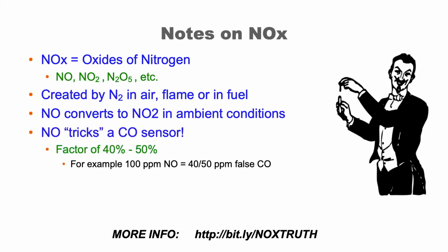The whole point of this is that nitric oxide, the NO component, tricks a CO sensor. It's also an acid gas. It makes the CO sensor think it's sensing CO. So for example, if you had 100 ppm nitric oxide, it would show up as 40 to 50 ppm false CO.